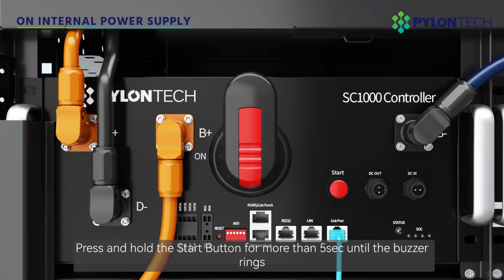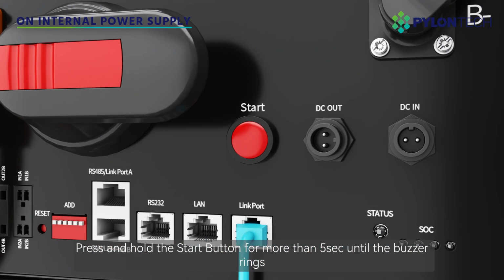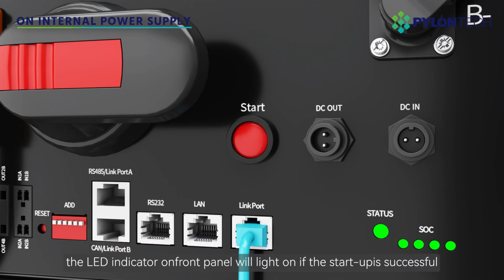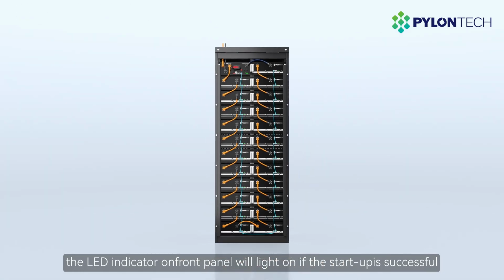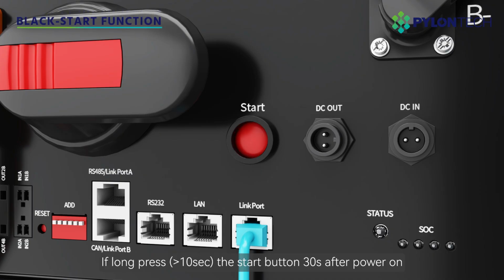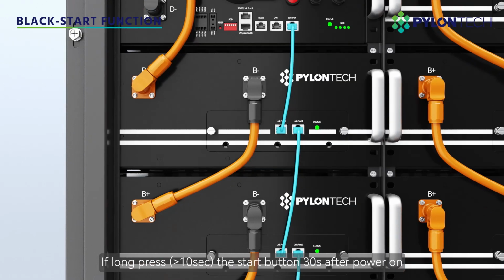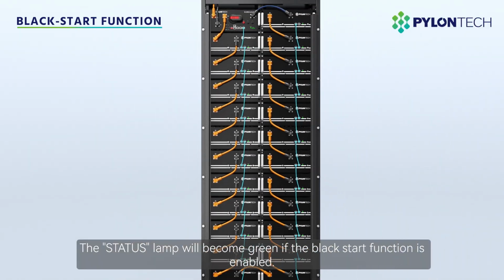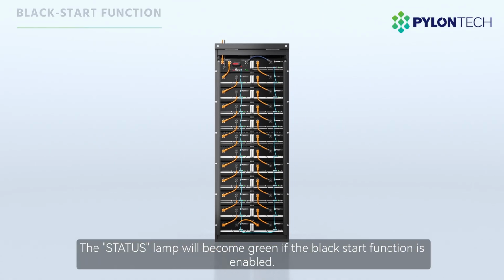Press and hold the start button for more than 5 seconds until the buzzer rings. The LED indicator on front panel will light on if the start-up is successful. If long press greater than 10 seconds, the start button 30s after power on. The status lamp will become green if the black start function is enabled.